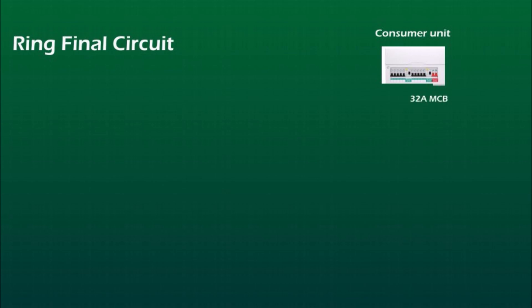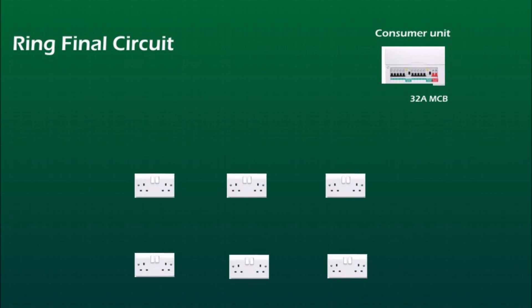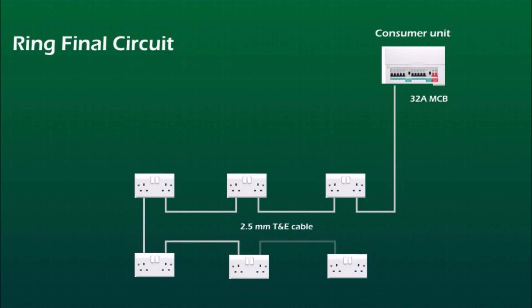Another commonly used circuit for socket outlets is a ring final circuit or simply ring. So again top right corner we've got the consumer unit with 32 amp MCB and let's say we've got six socket outlets on this ring. 2.5mm twin and earth cable from consumer unit goes to the first socket, then from socket to socket and from last socket the cable goes back to the consumer unit. The two brown live wires from both cables we connect to the same 32 amp MCB.